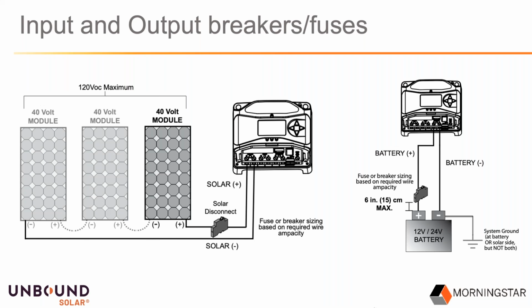You'd want to size this based on the size of the wire. And essentially the breaker's protecting the wire, so they need to be rated for the same current, or the breaker could be smaller than the wire's rating. So if that's number 10 wire, if it's number 10 PV wire coming in and it's rated for 30 amps, you would simply use a 30 amp solar input breaker or a fuse, but in most cases we'd recommend a breaker unless it's a very small system.